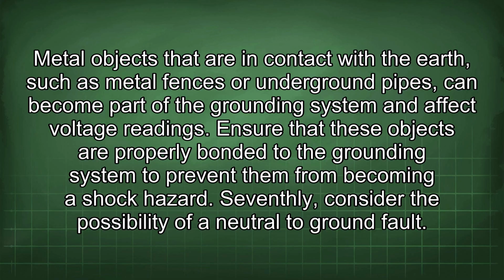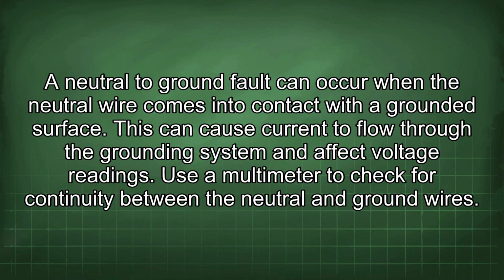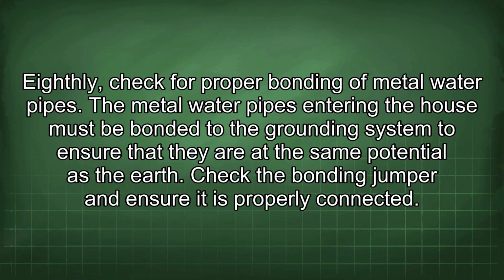Seventhly, consider the possibility of a neutral to ground fault. A neutral to ground fault can occur when the neutral wire comes into contact with the grounded surface. This can cause current to flow through the grounding system and affect voltage readings. Use a multimeter to check for continuity between the neutral and ground wires. Eighthly, check for proper bonding of metal water pipes. The metal water pipes entering the house must be bonded to the grounding system to ensure that they are at the same potential as the earth. Check the bonding jumper and ensure it is properly connected.